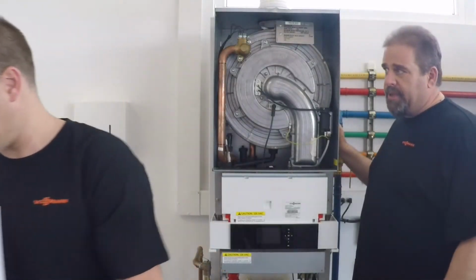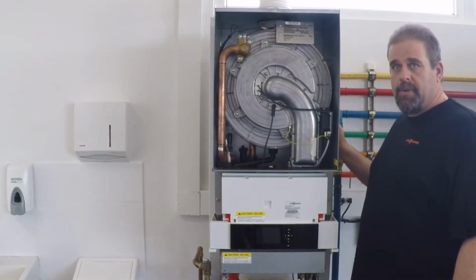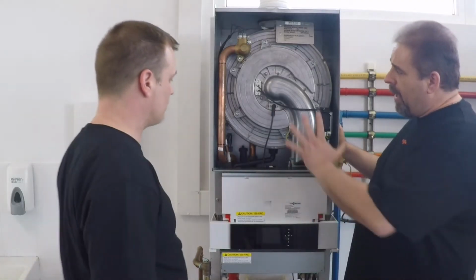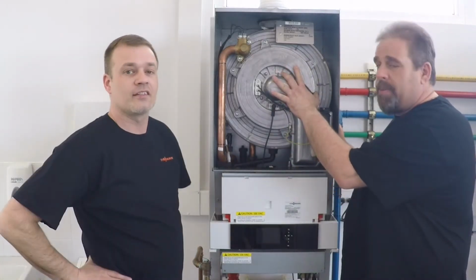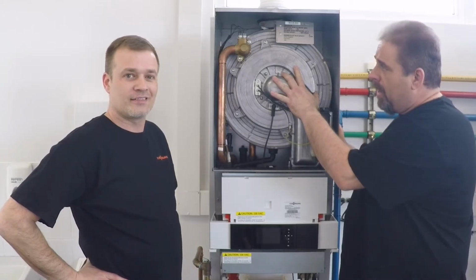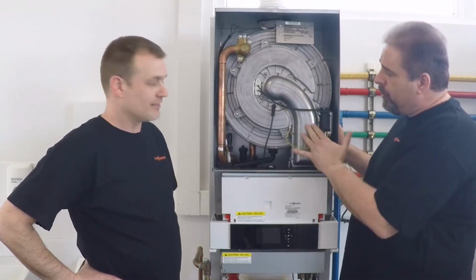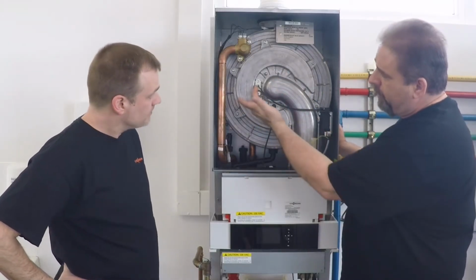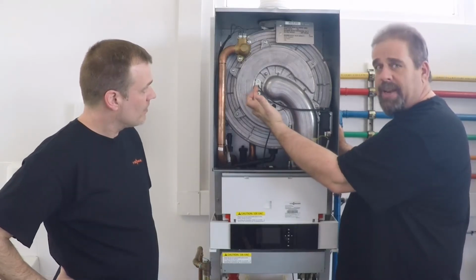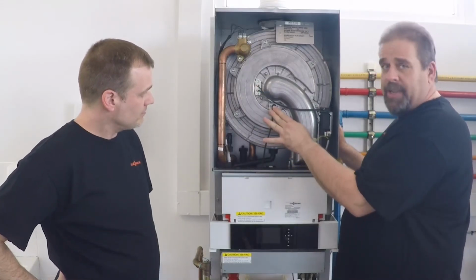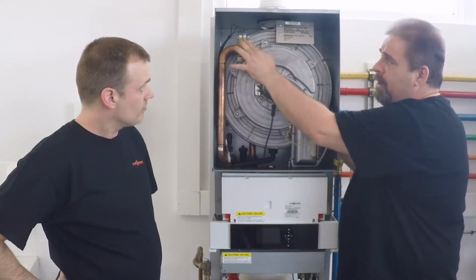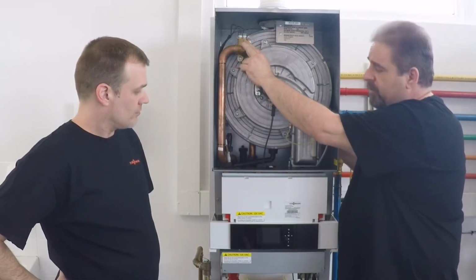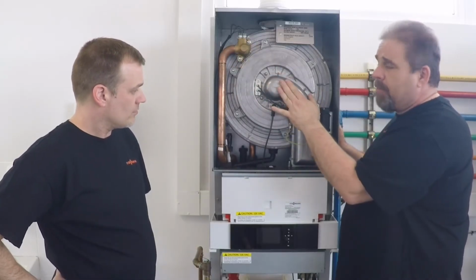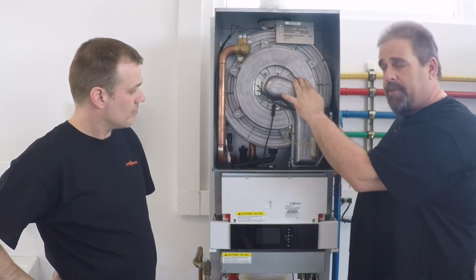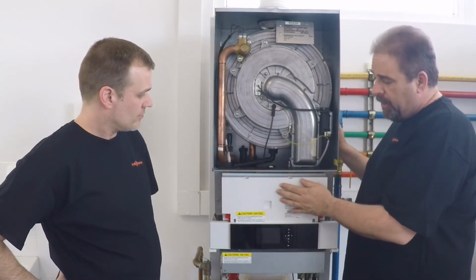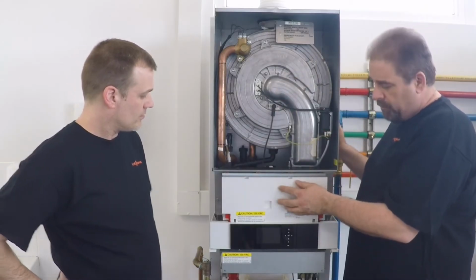set that down out of place, and now we see half of our premix burner assembly. We can access certain components now. We can actually get to an ignition electrode, an ionization electrode, also a number 3 boiler water temperature sensor. But to remove the burner assembly to access the heat exchanger for service, we need to lower the control console.